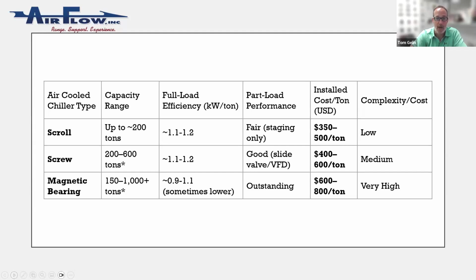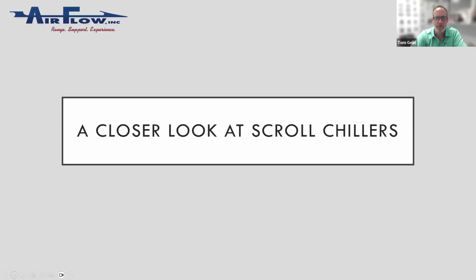As we go up in size and complexity, we get into screw chillers and then magnetic bearing chillers. The screw chiller's smallest size is actually 70 or 80 tons, right Ahmad? Yeah. So if you need more controllability, there's an option for you. And then finally magnetic bearings, we go all the way down to 70 or 80 tons and up to over 1,000, maybe 800. But we're going to cover those in a few slides anyway, so there's some costs and returns to consider.